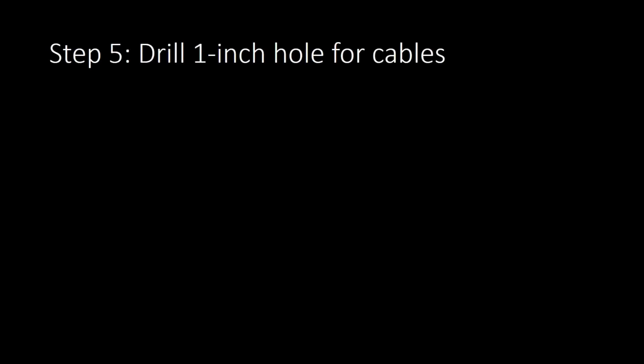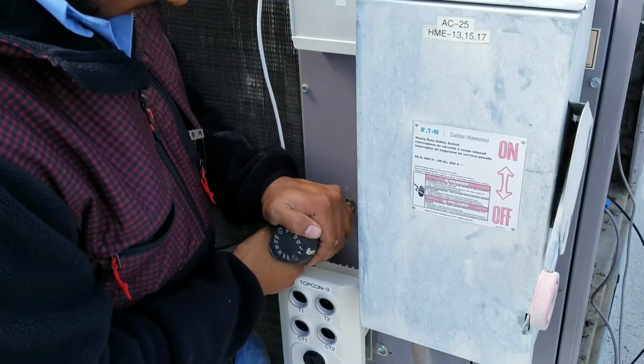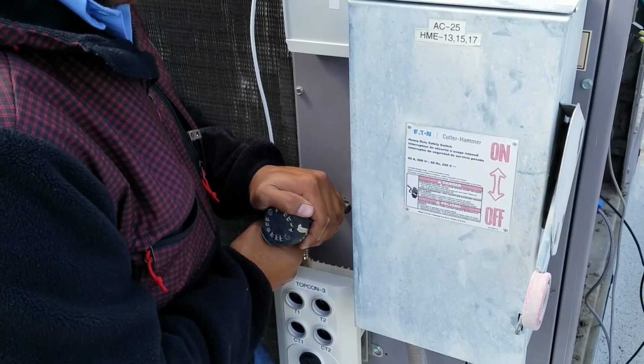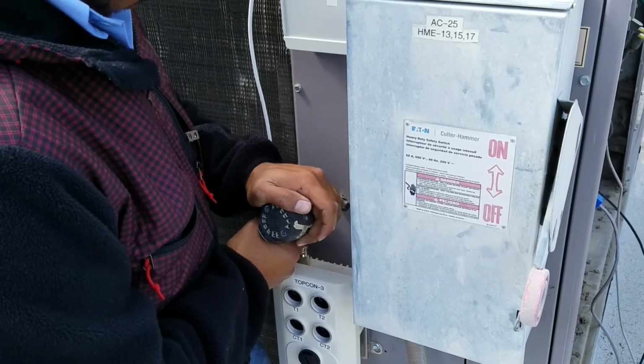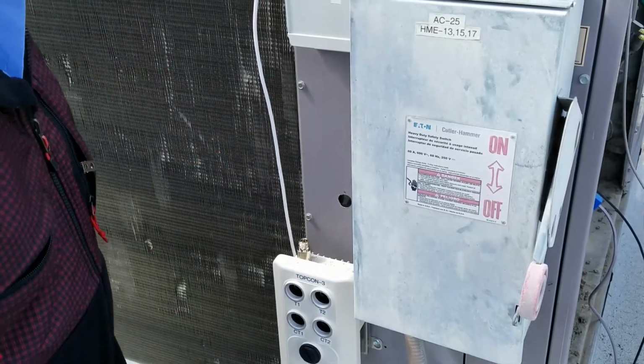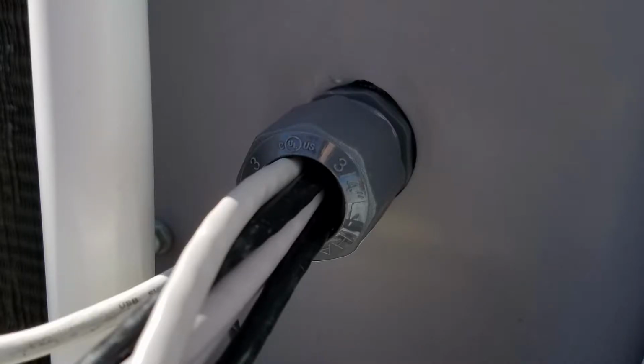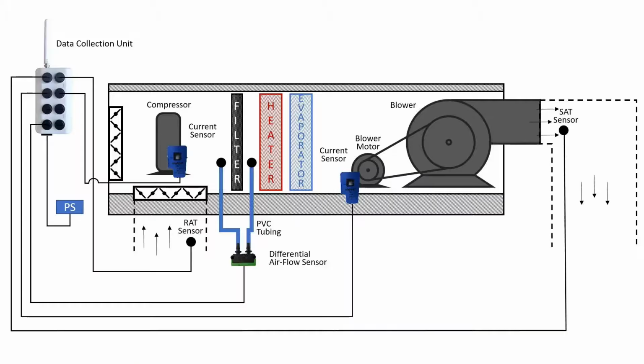Step 5. Mark a location for a 1-inch hole near the modem and DCU locations. This hole will be used for sensor and power cable access. Drill a 1-inch hole and install a cable gland. Step 6. Install sensors. Run sensor cables through the 1-inch hole to their final locations. This includes 2 CT sensors for the compressor and blower, 2 temperature sensors for the return and supply air, and 1 differential air pressure sensor for the filter.